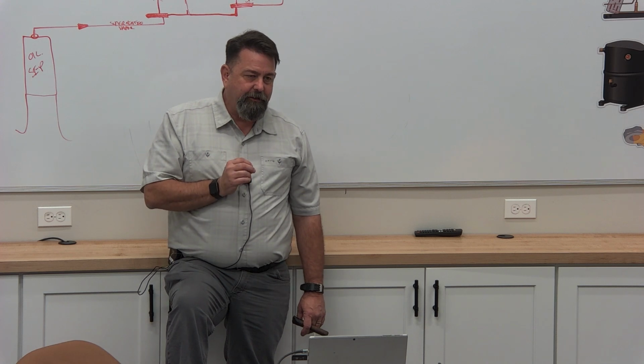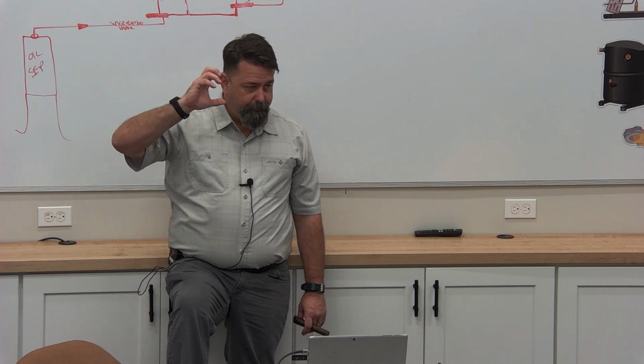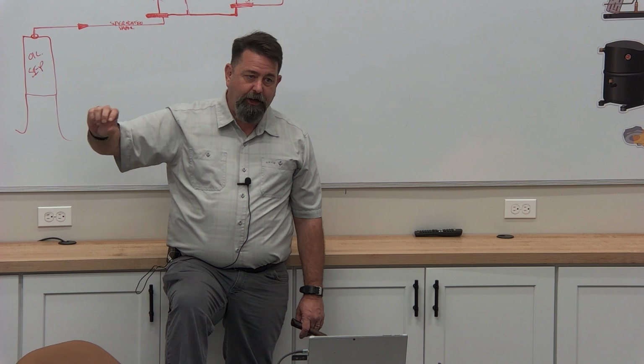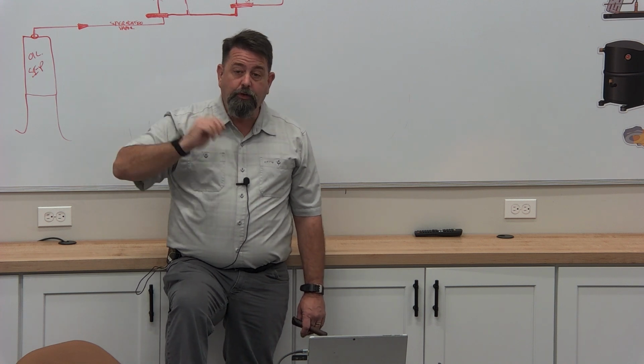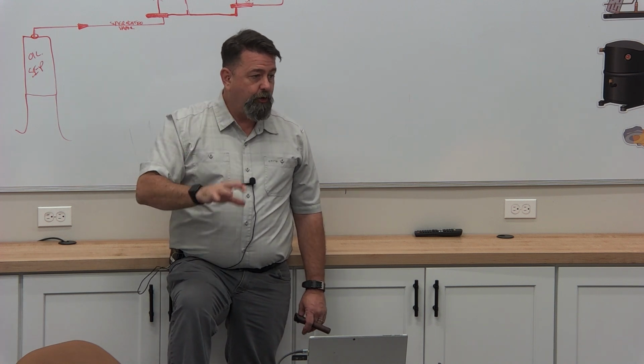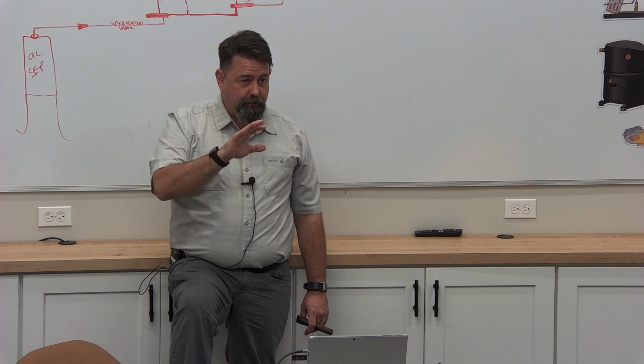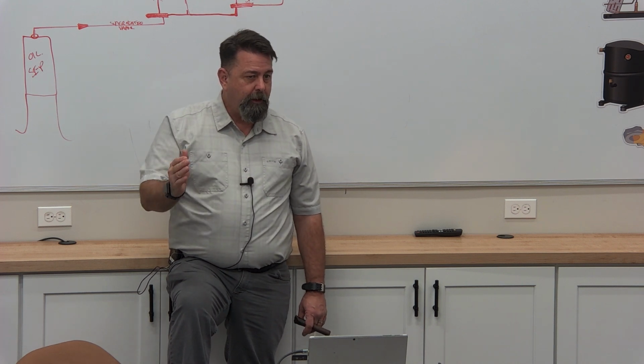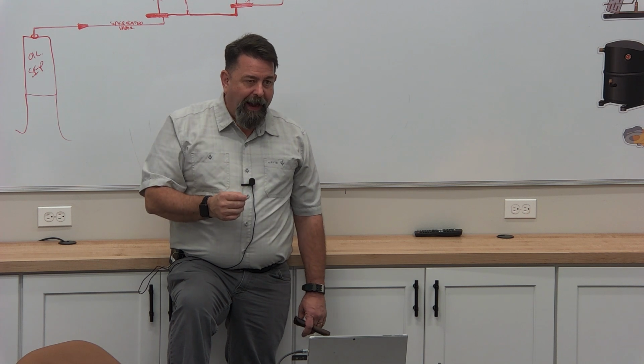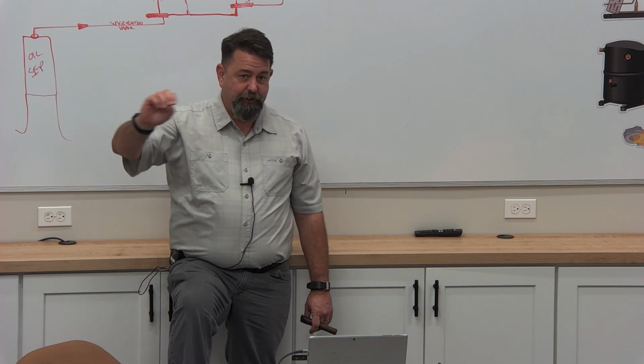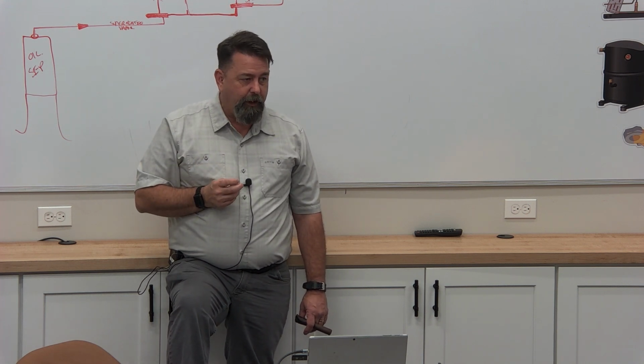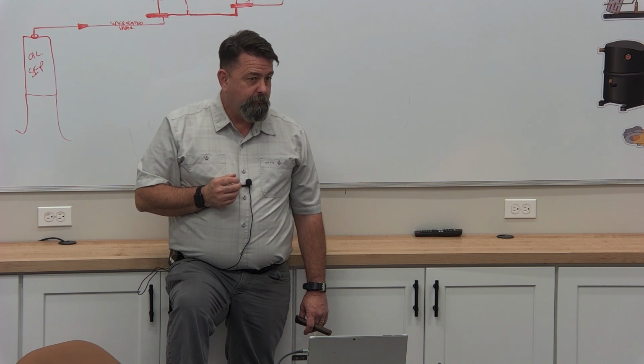So instead, my EPR dictates the pressure in my evaporator. Technicians are using a PT chart to convert temperature to pressure. My engineer started out saying he wanted a specific SST, he didn't say pressure. We kind of assumed that.